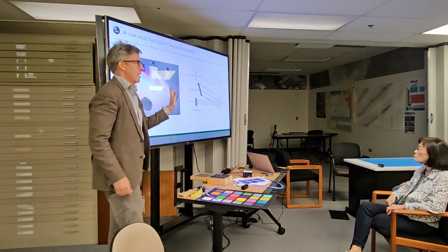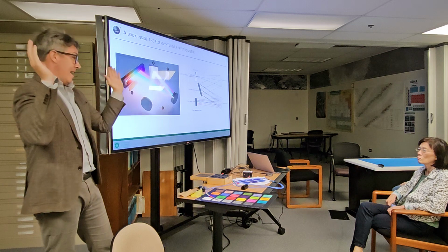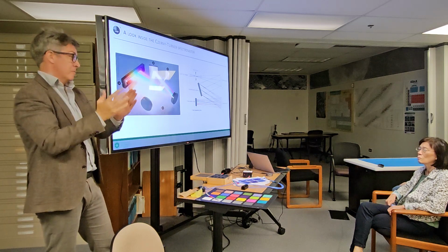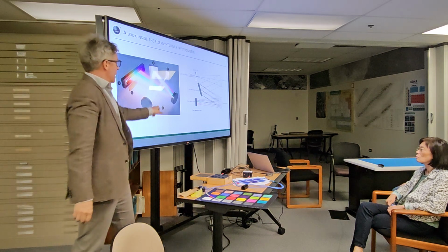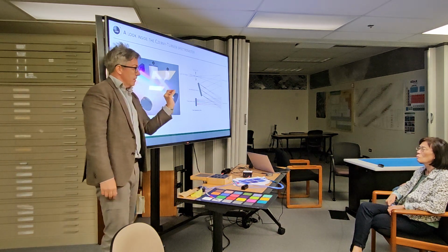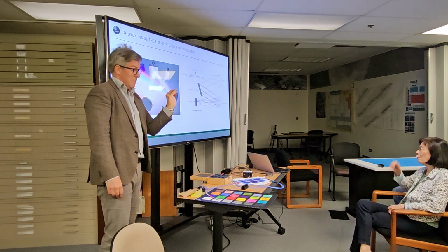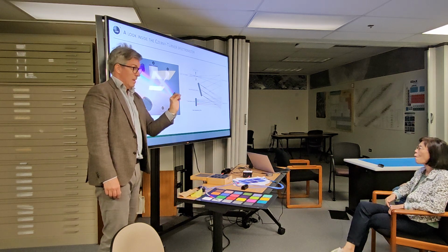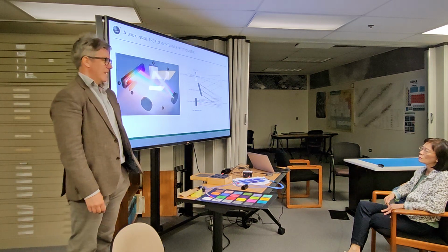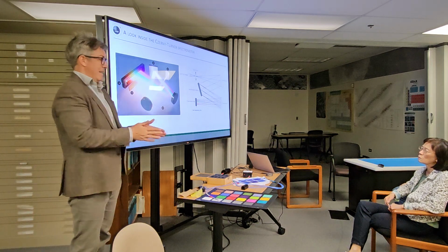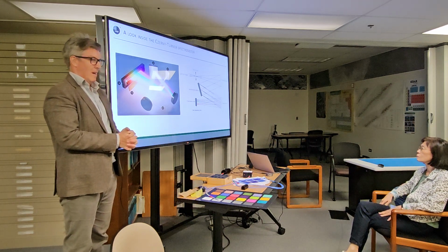The purpose of the slit is to reduce, well, there's several reasons. One is to reduce the angle over which you're receiving light into the spectrometer, to try and keep it from as narrow an angle range as possible. In spectroscopy, the narrower the slit, the higher the spatial resolution, right? In this case, the spectral resolution. It just means you have a narrower beam, right? Can you imagine what a narrower slit also does? If I make that slit really big or really narrow, what does that do to the amount of light that the spectrometer collects?